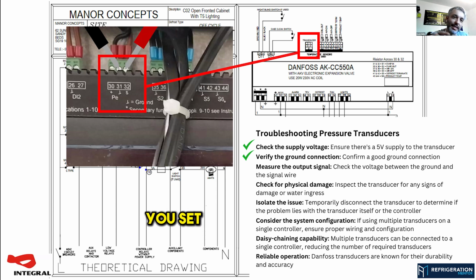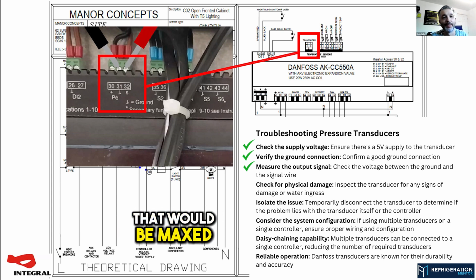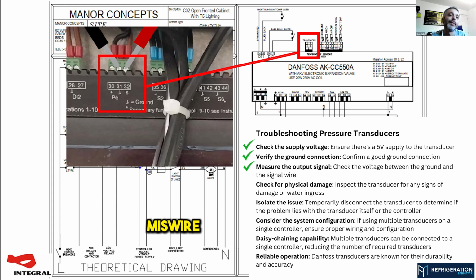And depending on what you set your transducer range to in the controller and what gas you select in the controller, it will give you your pressure and it will give you your calculated temperature from that. If you've got, let's say, for example, it's not running and you've got 5 volts on where you've got the probes there, that would be maxed out on the transducer. So you've either got a system that's stopped and your pressure is very high, or you've got a fault somewhere or a miswire.